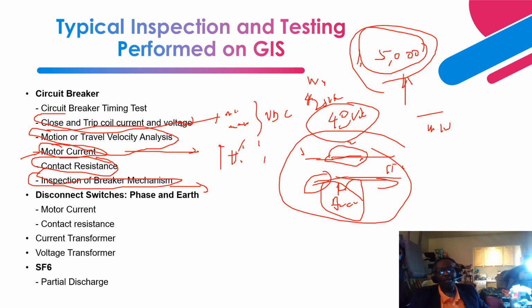Because remember, on one of my presentations, this GIS had been in operation for quite close to 10 to 12 years, and the circuit breaker cyclometer reading was about 100. So that itself tells you that it is far away from 5,000. So basically, inspection of a breaker mechanism is not necessary at that time. The GIS was due for a major overhaul. So that itself is based on condition. A condition-based assessment can basically extend the time-based maintenance from 10 to 12 years to 15 years. So that was one of my recommendations that I made on that presentation.